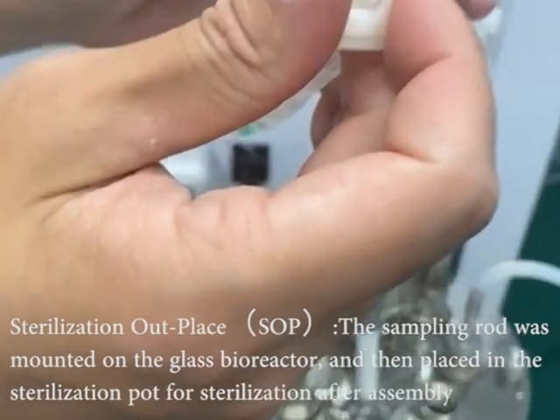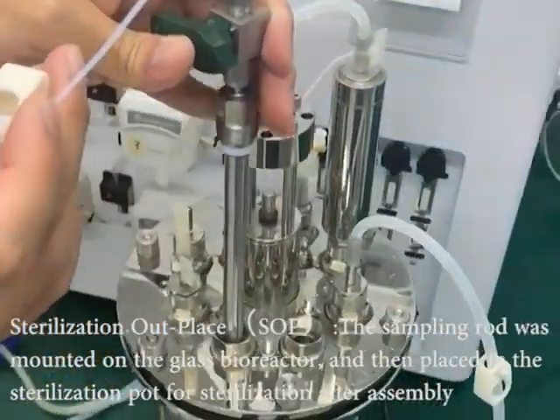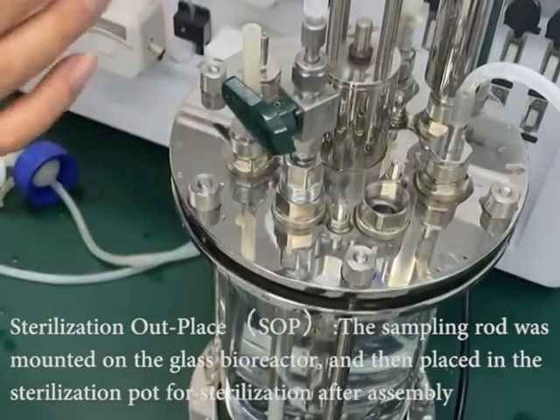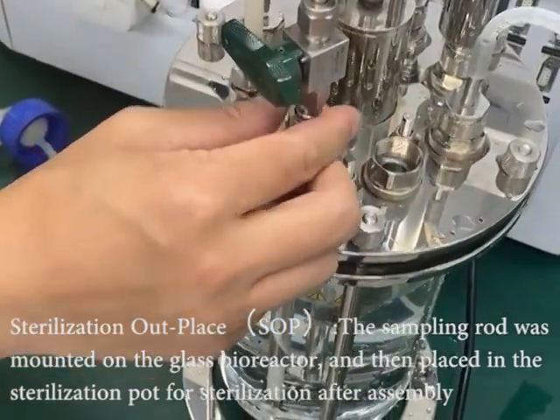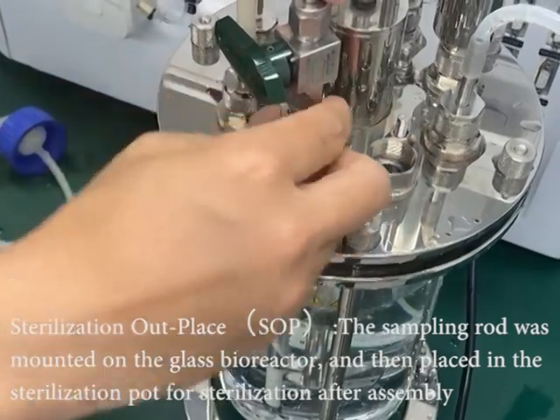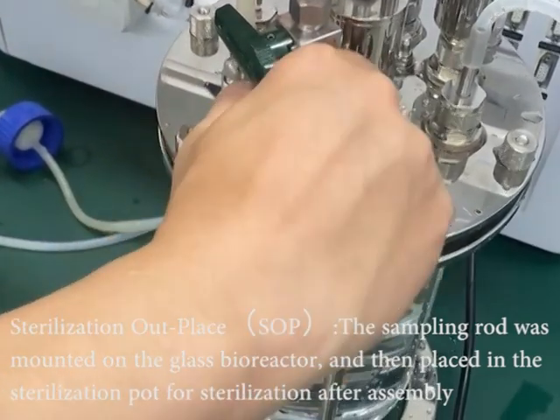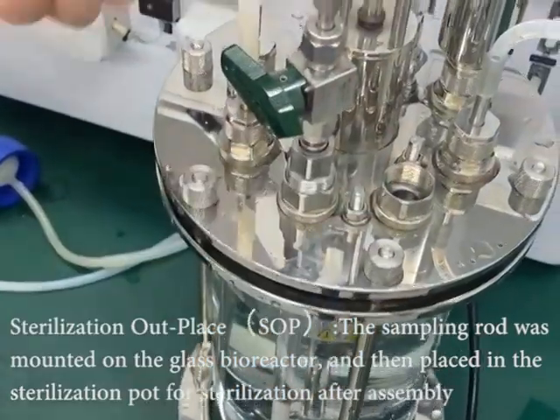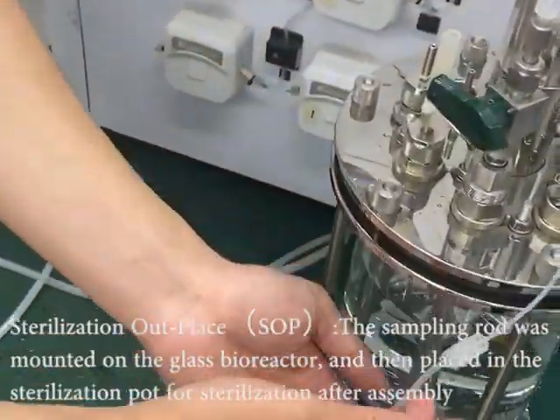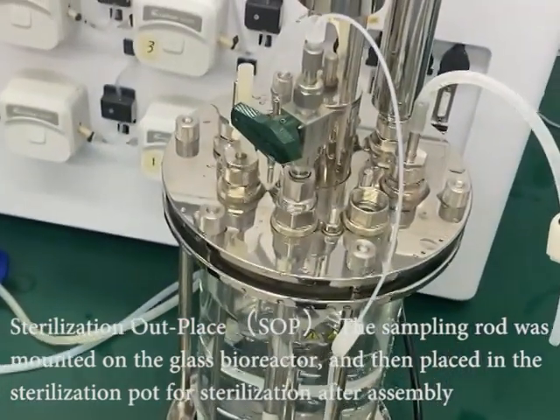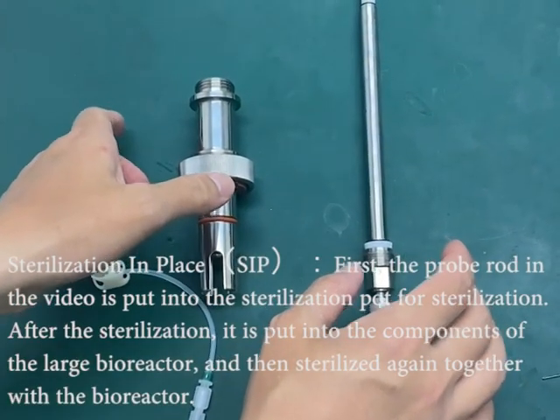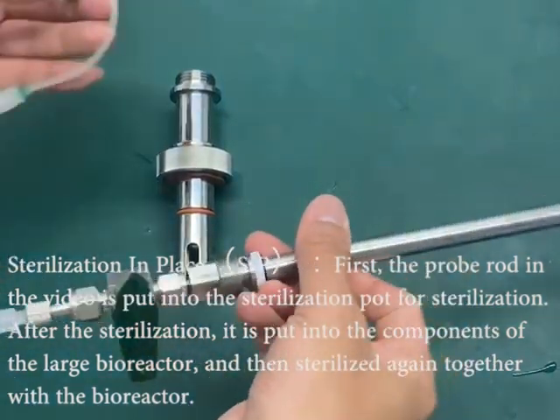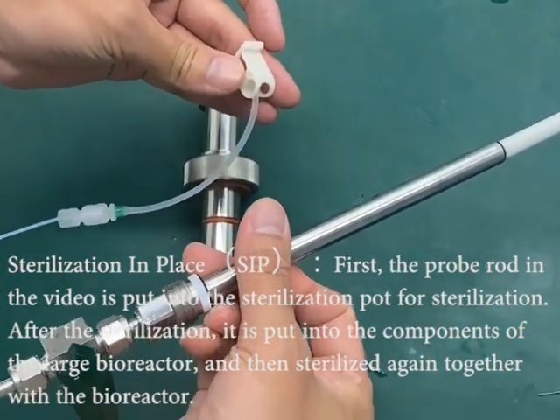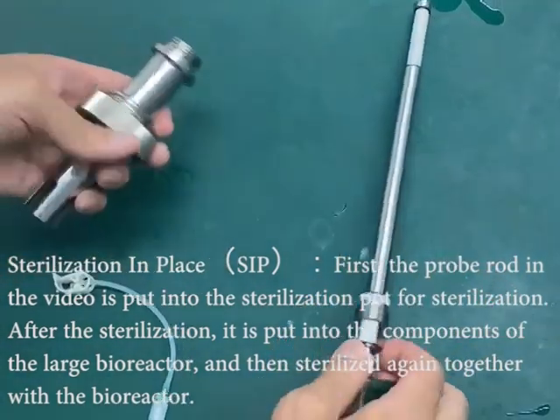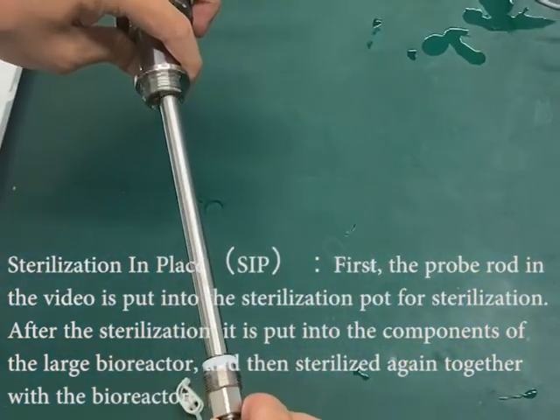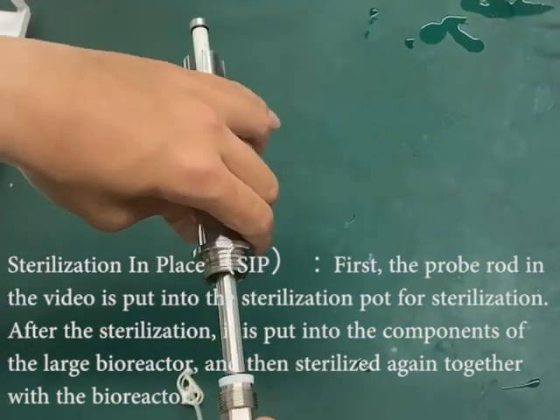Sterilization outplace, SOP: the sampling rod is mounted on the glass bioreactor, and then placed in the sterilization pot for sterilization after assembly. Sterilization in place, SIP: first, the probe rod in the video is put into the sterilization pot for sterilization. After the sterilization, it is put into the components of the large bioreactor, and then sterilized again together with the bioreactor.